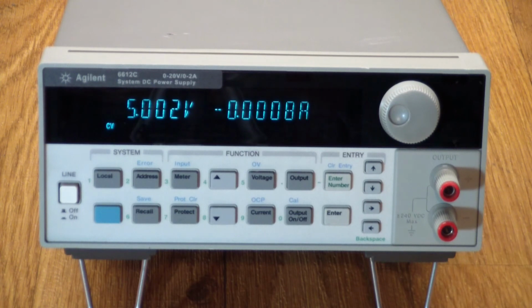The only mystery, of course, is how could a device that can supply 2 amps max blow its own 4 amp fuse? The only way it could do that would be if there was some major damage in the voltage regulation circuit. And since replacing the fuse, we see that it works just fine. So I don't think that this was caused internally, but rather by something hooked up to it externally that forced a current of more than 4 amps into the device and thus blew the output fuse, because the output fuse sits directly on the positive terminal. So I'll call that mystery solved there, and we have a working power supply.